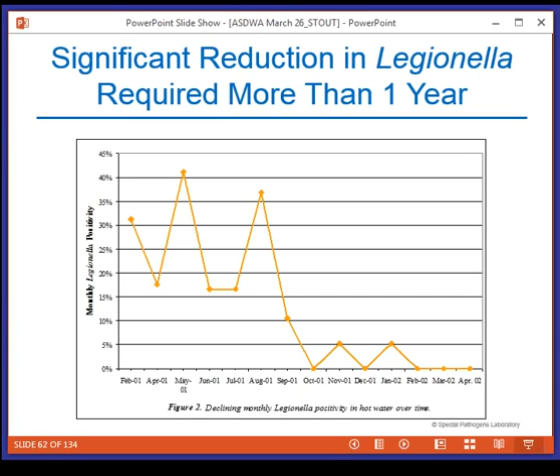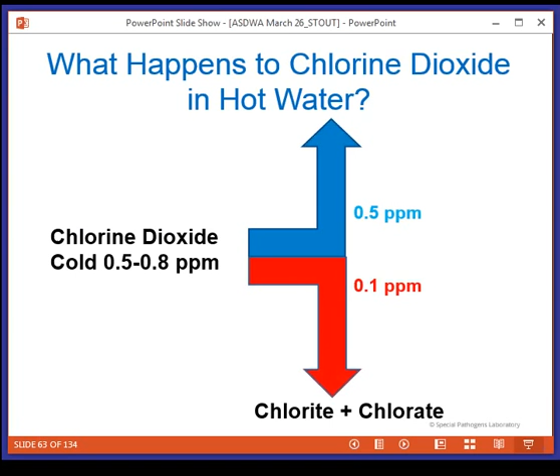So why does it take so long? I was sort of scratching my head. The kinetics of chlorine dioxide in hot water explains the reason. You put chlorine dioxide in at 0.5 to 0.8, 0.8 being the maximum allowable amount. When it goes over to the cold water side of the building, you maintain that level nicely. But when it goes over to the hot water system, it essentially disappears and breaks down into its byproducts, chlorite and chlorate. That explains why, where Legionella is living in the warm water part of the building, if you put chlorine dioxide on the cold water alone, it's going to take a long time. It's essentially your CT value, concentration times time. So that explained why it took so long.